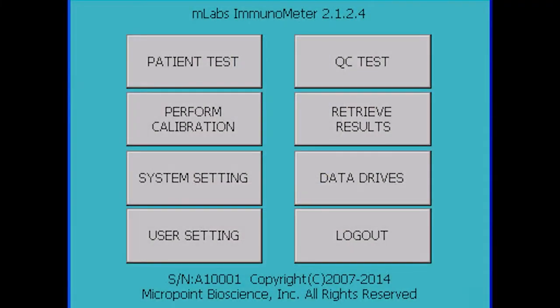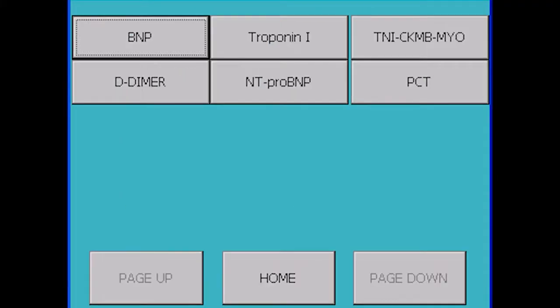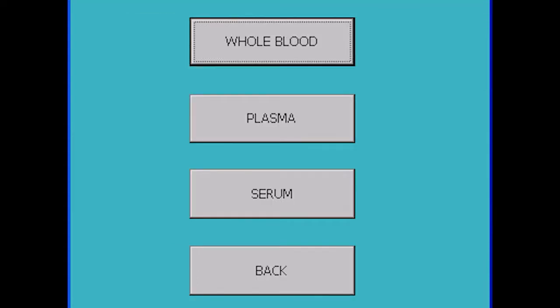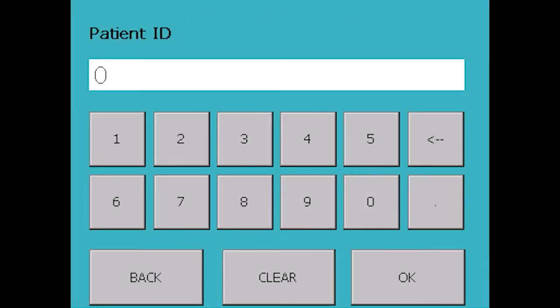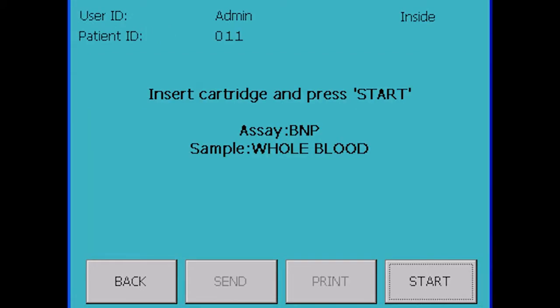From the main menu, touch Patient Test. Select the assay type as shown. The screen will display the sample type after you select the assay type. Enter up to 15 digits for a patient ID. Tap OK to advance to the next step. The MLabs ImmunoMeter will display a test menu.